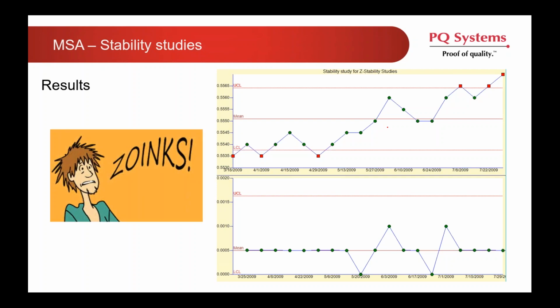So this would be a shock, and we would want to, A, do an emergency calibration as soon as we identify it's trending in one direction, and that's all evidence that we could use to further the idea of, look, maybe we need to ratchet this calibration interval back to maybe the 3-month mark because that's around the time it started to fail. So we're trying to zero in on the appropriate interval where we're not doing it too often or too seldom. We're trying to get to that Goldilocks zone where we calibrate it right before there's a problem.